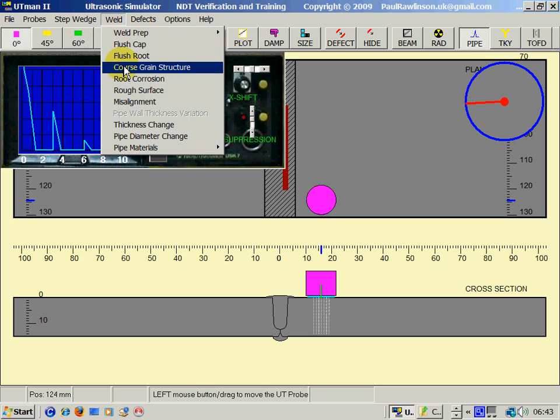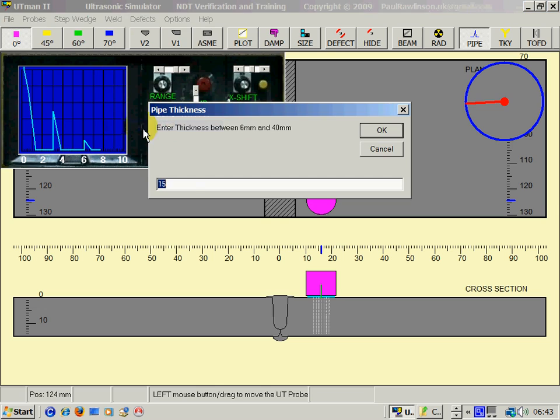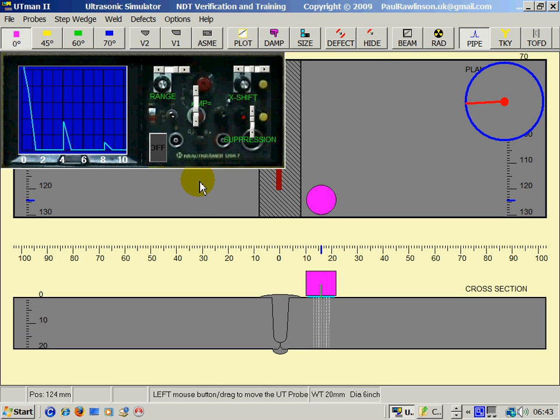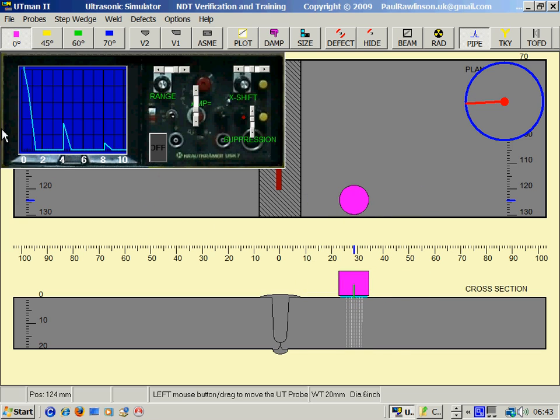To increase the weld thickness we go on the menu. This time I will set it for 20mm weld thickness. We can see the echo is coming up at 20mm distance.